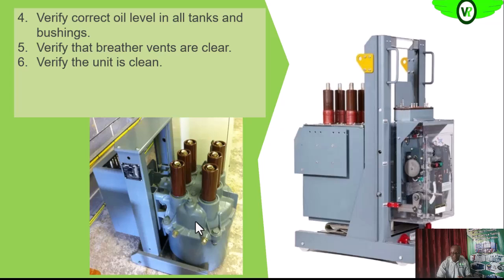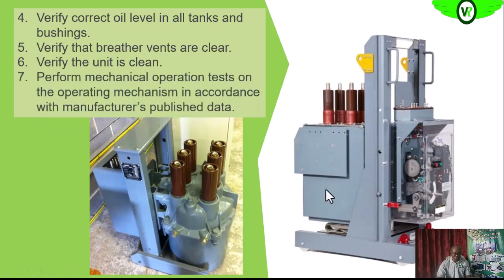Then we want to look at the entire unit to see that it is free of debris and very clean. If there is debris, we need to clean the unit up before we proceed. Then we also want to cycle the circuit breaker, carry out mechanical operations, just to be sure the operating mechanisms are operating properly, in accordance with the manufacturer's recommendation or laid down procedures by your facility.